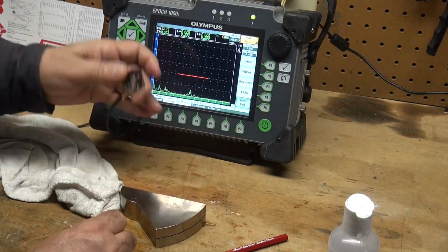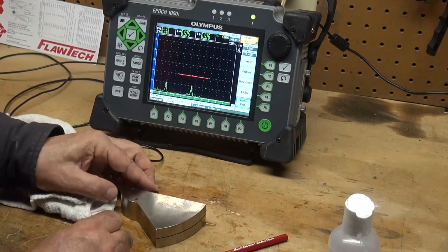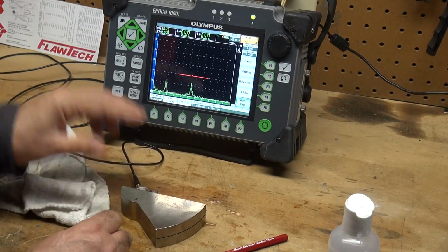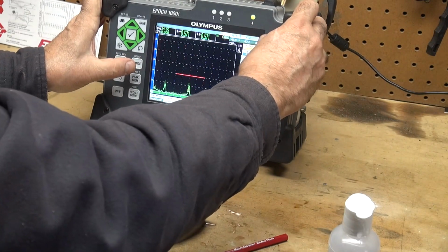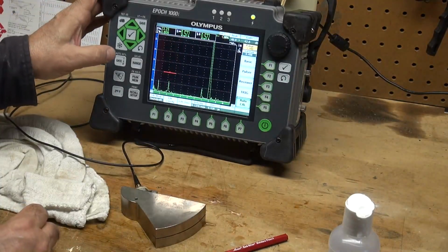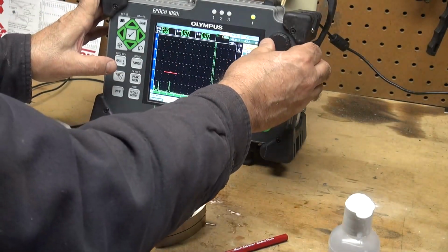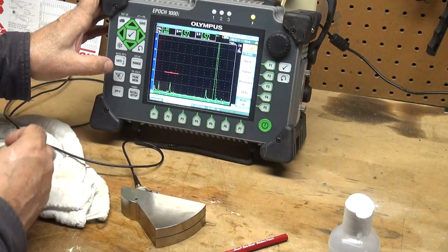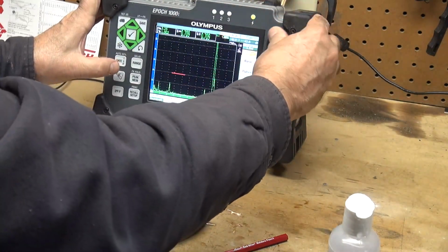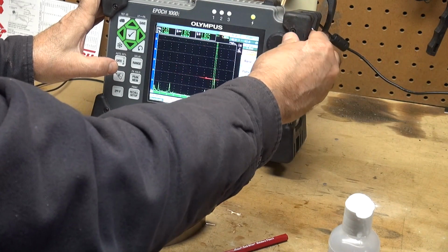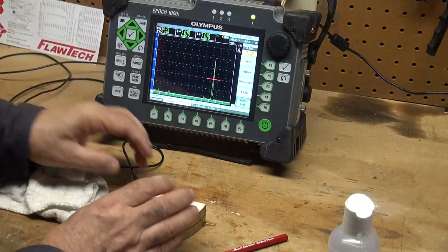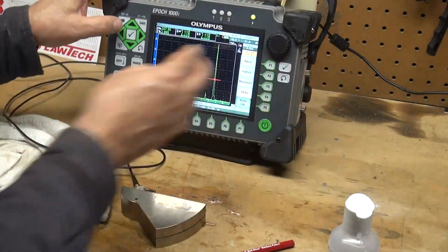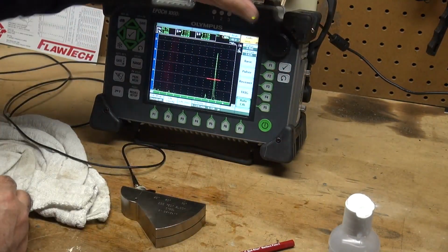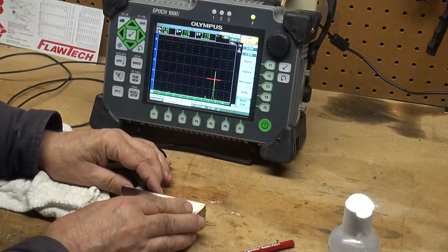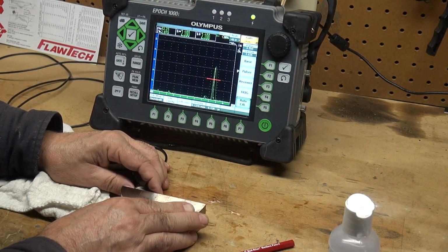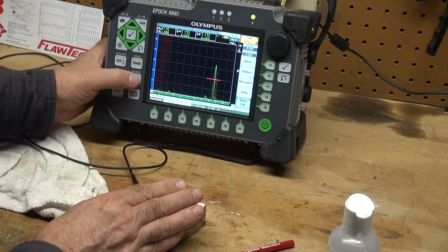Now to set our reference level, we want to look at our 3-inch radius here. So let me open up my range so I can see that 3-inch radius, and there it is right there. I'm going to set this guy at 3.5 inch sound path. Move my gate over here and bring this guy down to 80% full screen height. Let me peak him. My gain's a little bit hot. Bring it down a little bit more. And let's peak that signal. Right there. So that's my 3-inch radius. My sound path reads 3 inches.